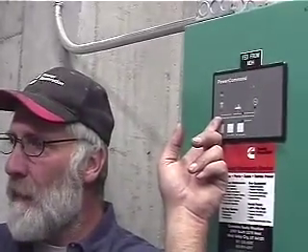Usually, like I said, 2 seconds, and a 10-minute retransfer time, so it's going to look at this here once this light comes back on for 10 minutes to make sure you have good power. Before it says, okay, we're good power, then this light's going to go out, now that's going to come on and be transferred back. And you're going to hear 2 big clunks when it does that.